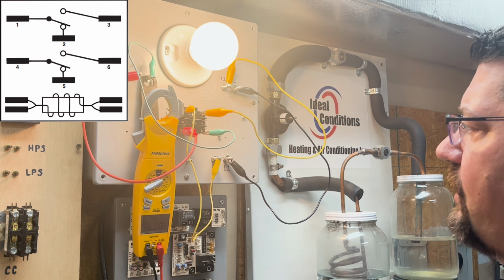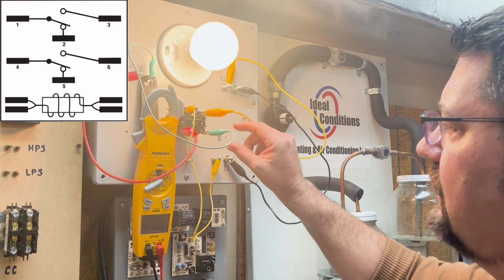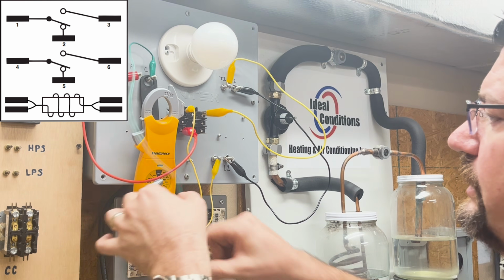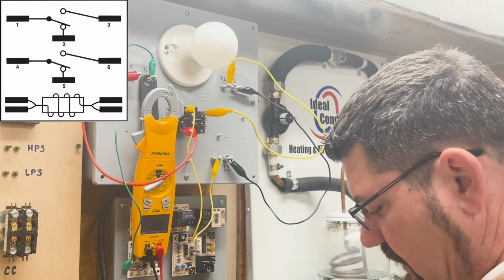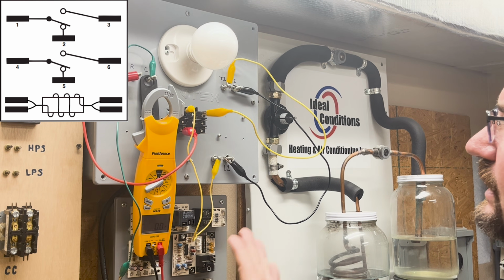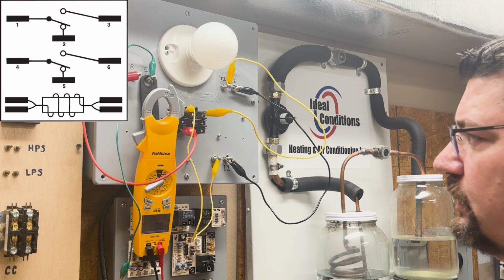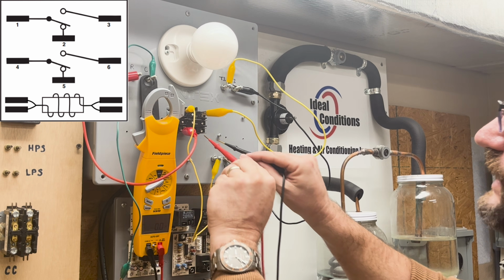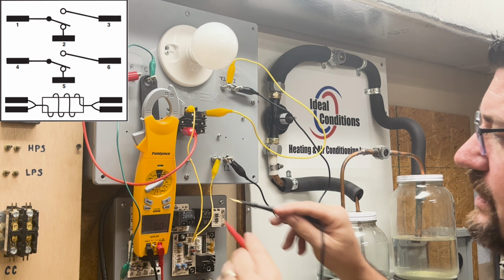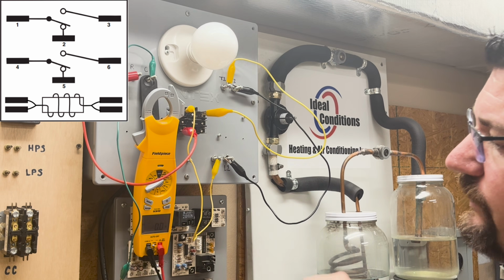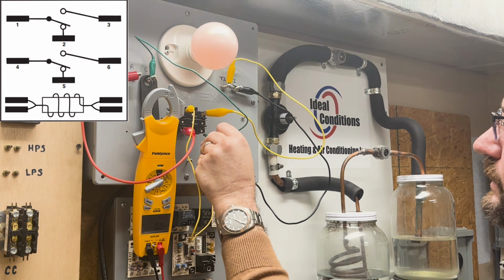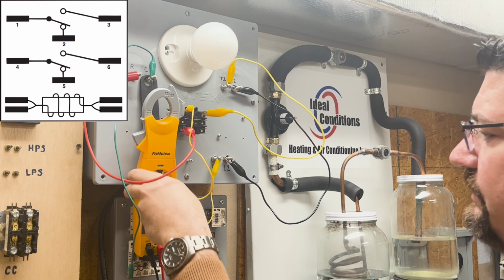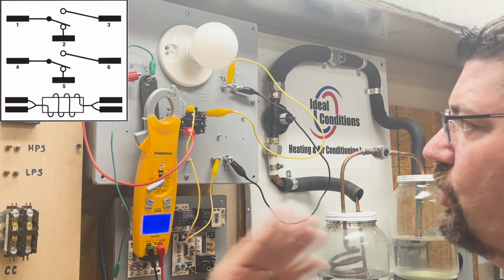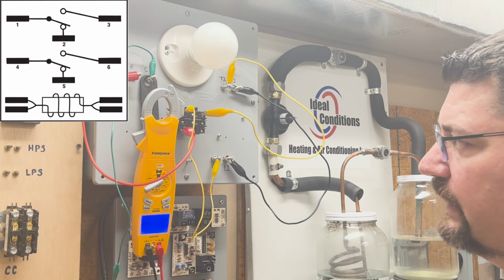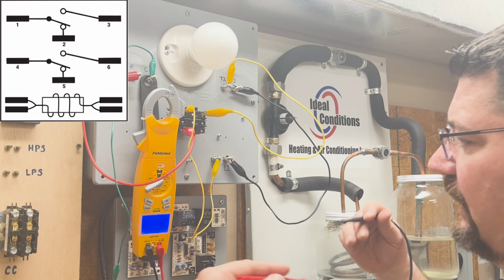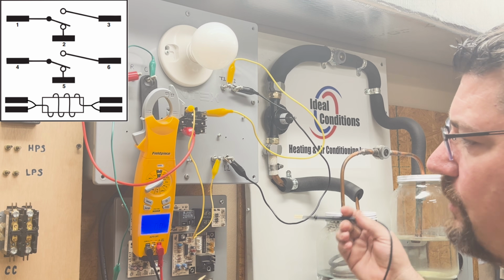Okay, and now if I were to take 24 volts off of my relay and I wanted to see, is my relay open or closed? Say I can't get down here to see if there's 24 volts present. We know by what we're doing there's no 24 volts present because we just removed it, right? But let's just say we wanted to find out just by using our meter, because your meter is a tool. It tells you when things are open, when things are closed, when there's power present.